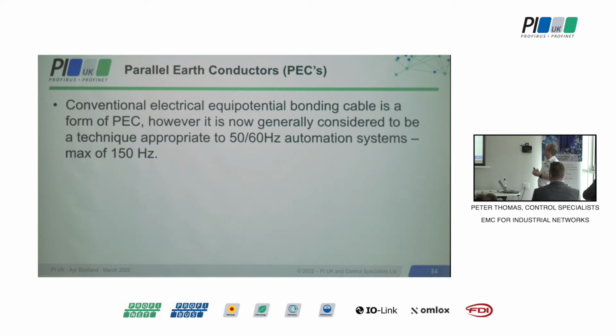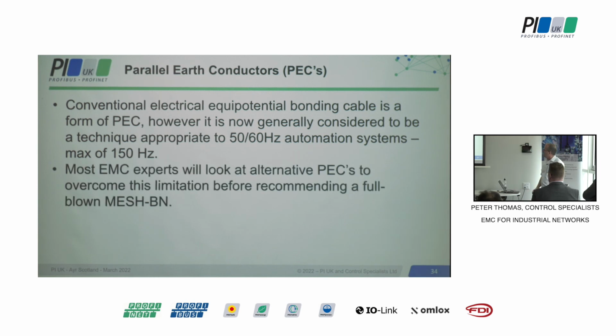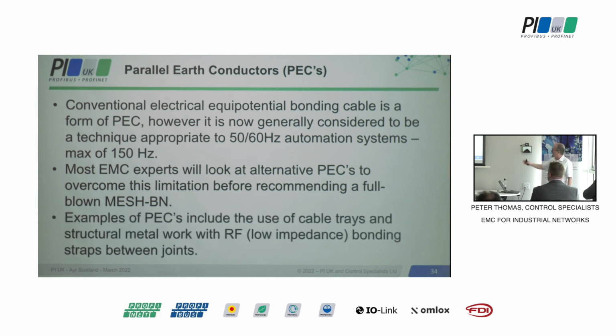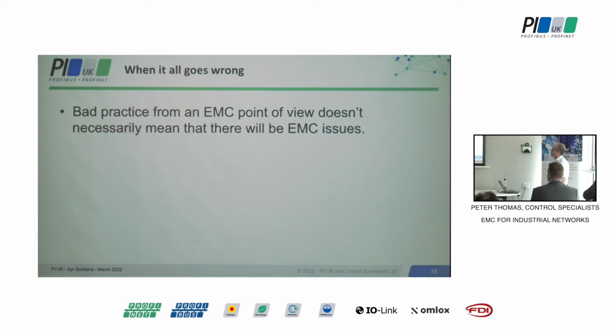This is all described in these standards. Basically, the use of green or yellow wire for 50, 60 hertz is fine, but they also look at alternative PECs. Nobody's going to start digging new holes in the ground to improve EMC, and nobody's going to do a site-wide bonding infrastructure. They will look at how to lower the potential between these two points. This 20-odd-year-old document tells you exactly how to do it - it could be the cable trays, the structural metalwork, and low impedance bonding between straps.